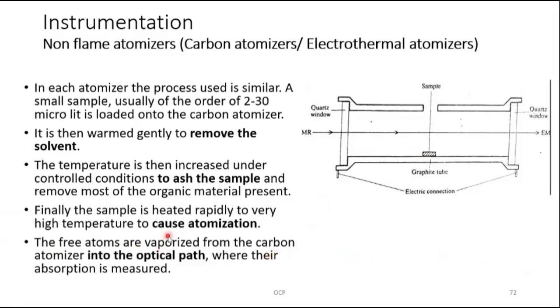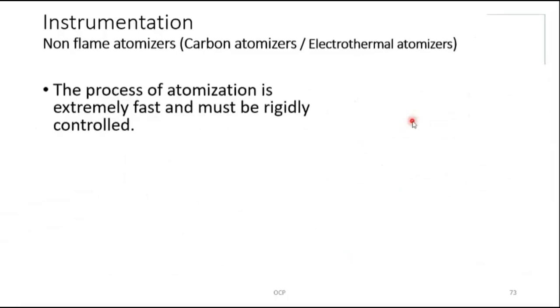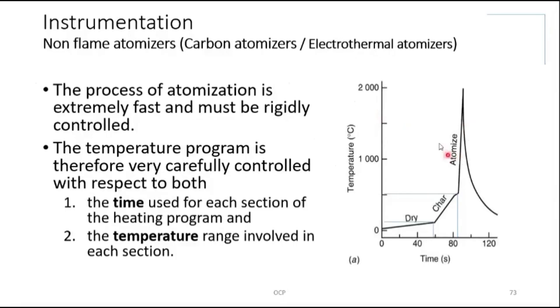The free atoms are vaporized from the carbon atomizer into the optical path where absorption is measured. The process of atomization is extremely fast and must be rigidly controlled. On a time–temperature diagram: the x-axis is time, y-axis is temperature. Drying is slow — taking approximately 60 seconds.